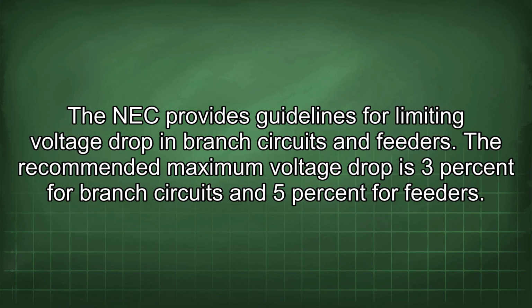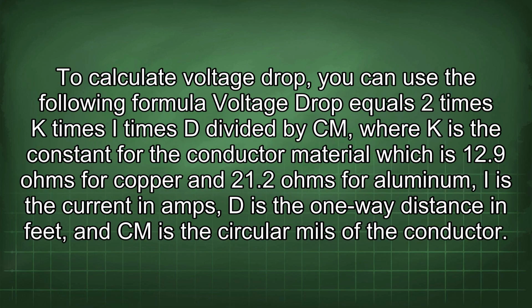The recommended maximum voltage drop is 3% for branch circuits and 5% for feeders. To calculate voltage drop, you can use the following formula: voltage drop equals 2 times K times I times D divided by Cm, where K is the constant for the conductor material, which is 12.9 ohms for copper and 21.2 ohms for aluminum, I is the current in amps, D is the one-way distance in feet, and Cm is the circular mils of the conductor.